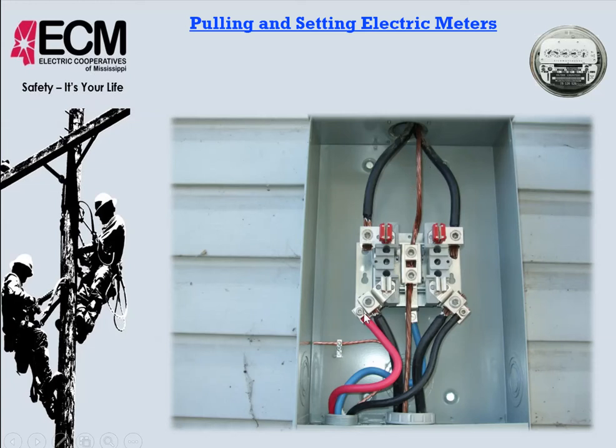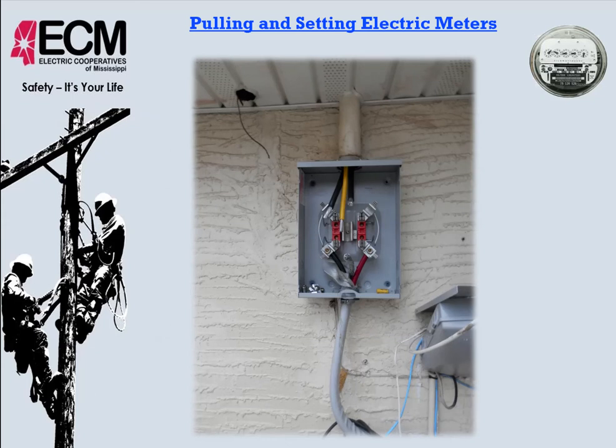I also like this meter base here that it's double lugged here. If we did have to go two directions, here's one pipe going one place, another pipe going somewhere else, so it's double lugged here. Also double lugged on the neutral side here, so that would help solve some of the issues that we had with the previous meter base. But there again, if it's in the conduit, it needs to be insulated, just like the others, the hots are.